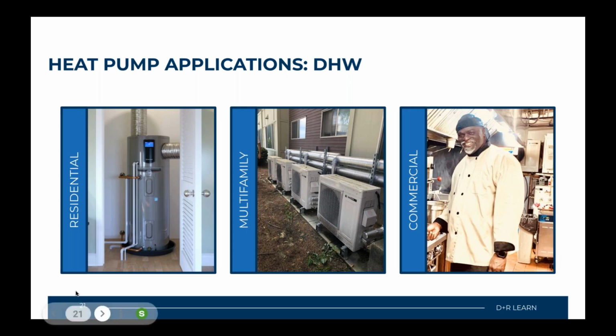Just a few quick statistics on these domestic hot water heat pump water heaters: the heat pump used in the commercial kitchen and in the multifamily building is the SanCO2 heat pump. These heat pumps are capable of producing hot water down to -20 degrees Fahrenheit, and the water temperature delivered can be up to 175 degrees. The system uses CO2 as the refrigerant, which is ozone-friendly and ranks very high on our list of refrigerants. We have a chart we'll go through that shows which refrigerants are eco-friendly and which are not.